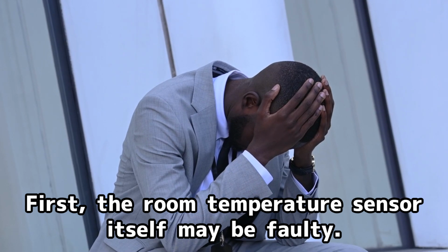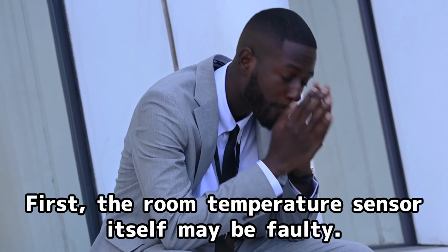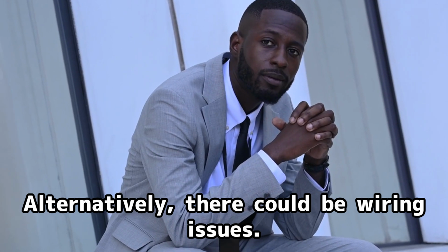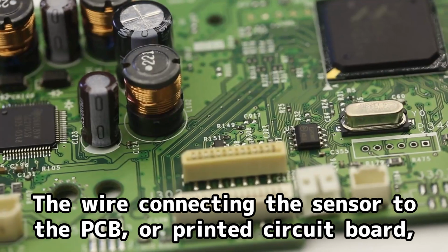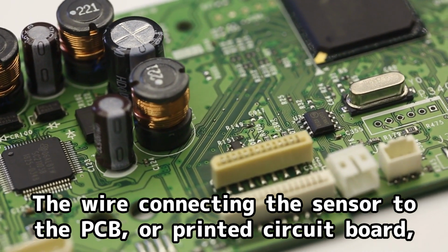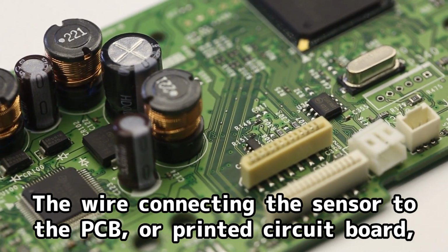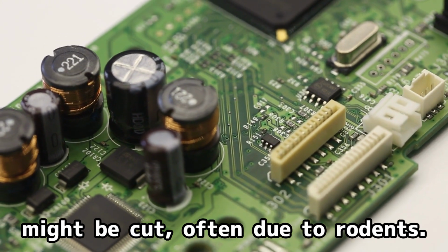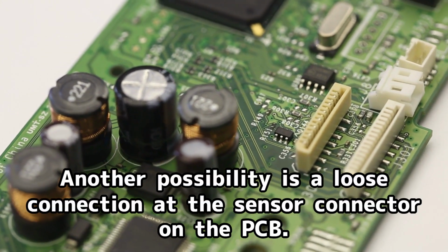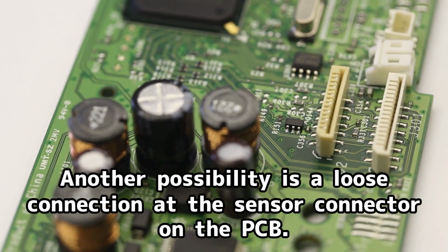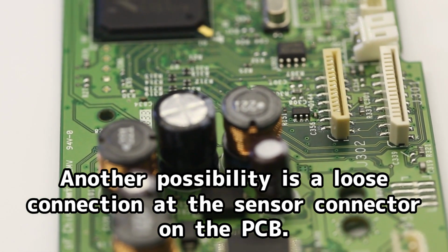First, the room temperature sensor itself may be faulty. Alternatively, there could be wiring issues. The wire connecting the sensor to the PCB, or printed circuit board, might be cut, often due to rodents. Another possibility is a loose connection at the sensor connector on the PCB.